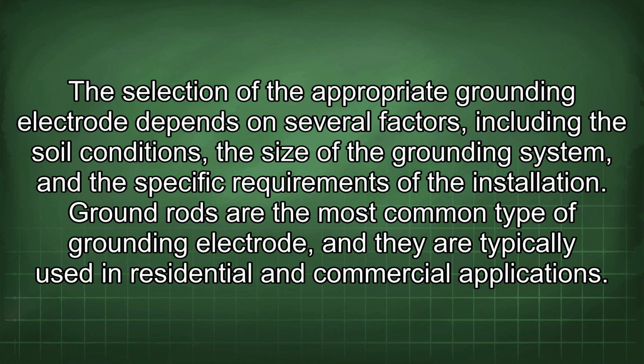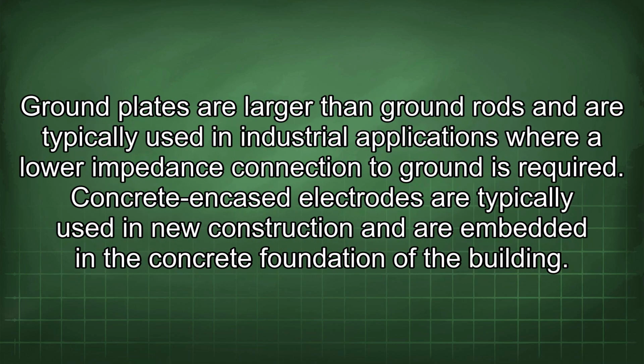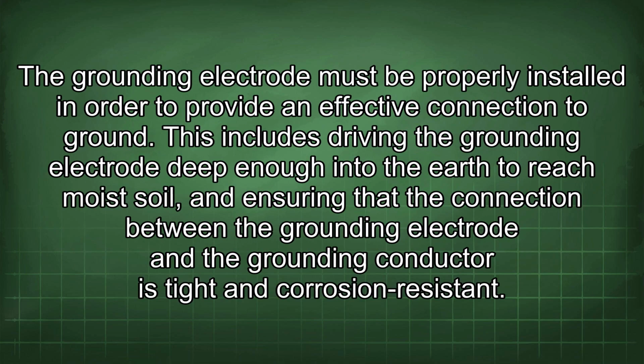Ground rods are the most common type of grounding electrode, and they are typically used in residential and commercial applications. Ground plates are larger than ground rods and are typically used in industrial applications where a lower impedance connection to ground is required. Concrete encased electrodes are typically used in new construction and are embedded in the concrete foundation of the building. The grounding electrode must be properly installed in order to provide an effective connection to ground.